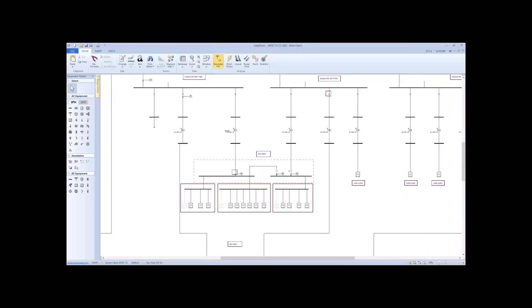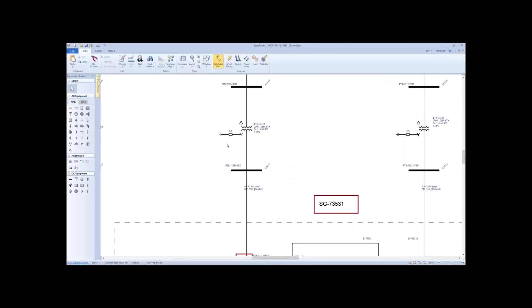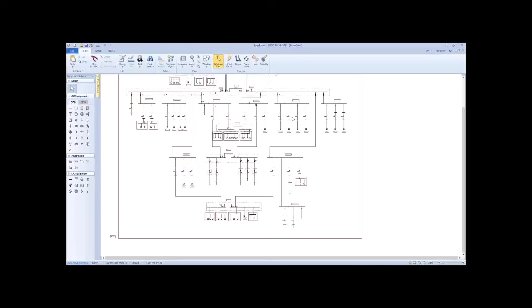I got a question. I noticed you use resistor neutral grounds on your transformers. What's the reason for that, or the justification? I'll show you something interesting about that, since I was working on it recently. Basically, Jim, we connect a grounding resistor to decrease the short circuit current. This is the main reason. Usually with medium voltage transformers, it's more common to use secondary side grounding resistor to decrease the short circuit current. In this project, we have grounding resistors in all power transformers and all generators, but in other projects I usually include grounding resistors only in medium voltage transformers, from 34.5 to 4.16 kV. In this case though, our neutral grounding resistors are everywhere.